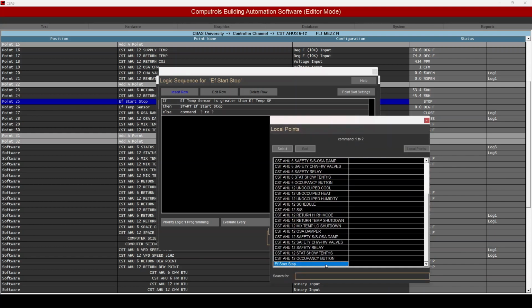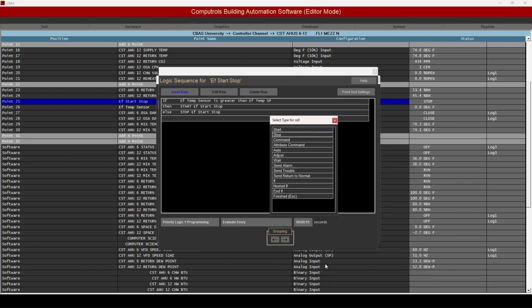Before I pick this, note a couple things. One, you're seeing point names — you're not building or defining an equation, you're working with the actual point names. Two, it doesn't matter whether this point's on a Computrols controller or Siemens or Johnson Controls — your logic and calculations are seamless. Three, when I say I want to start or stop something, the system only shows me potentially valid choices, so it won't show me a temp sensor because I can't start or stop that. It helps guide you to the right decision.